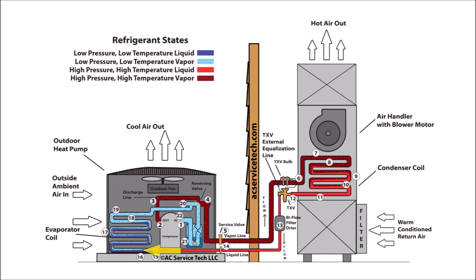This liquid is going to quickly change into a 20% vapor, 80% liquid state as seen at step sixteen. This is due to the lack of pressure and the availability of space within the tubing. At step sixteen, the refrigerant enters into the evaporator, and at that point the refrigerant is low enough in temperature to start absorbing heat energy from the outdoor air. As the refrigerant absorbs that heat energy from the outdoor air, it is not rising in temperature, but it is able to store that heat energy within the saturated state. The saturated refrigerant moves through the evaporator coil absorbing heat energy but does not rise in temperature. It continues through past step seventeen, with the amount of liquid decreasing and the amount of vapor increasing until it comes into the completely vapor state at step eighteen.